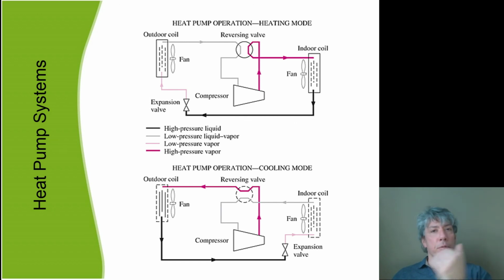Now that low temperature refrigerant can be used for cooling the indoor air, so it picks up heat. Understand again that we only allow vapor to come out of this, so that the liquid that has potential for more cooling remains in the coil until it is evaporated. And then you see it go through the reversing valve horizontally along that gray line back to the compressor, so that it's only vapor going into the compressor, or gas, and then the compressor completes the cycle we considered.